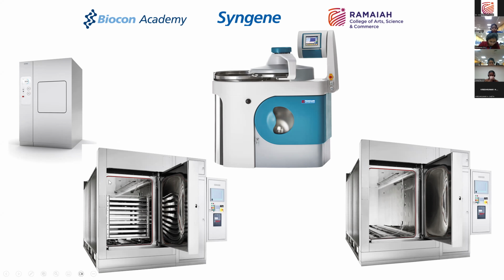You will then collect those strips, knowing the location, and say whether I achieved the kill rate which I was aiming for or not. I ran the cycle for 18 minutes. Ideally, it should have gone to a 0 kill, but for some reason it has not gone. Then I need to look at how I have placed my loads. Is it too tight? Is it touching each other? As a result of which steam is not able to penetrate.